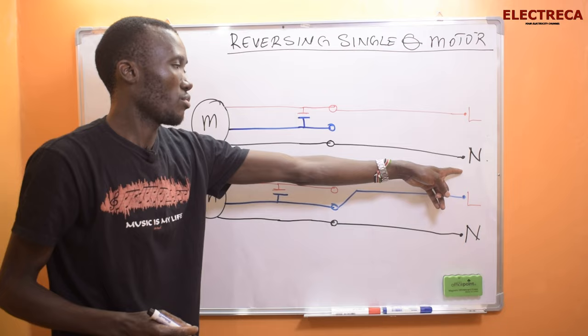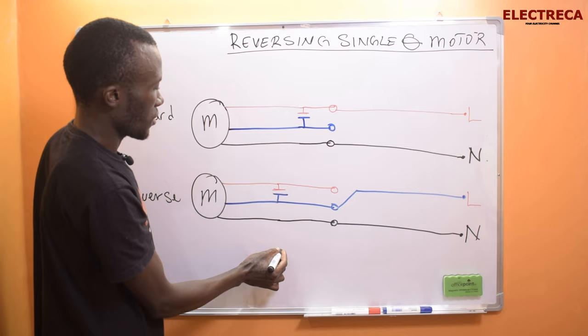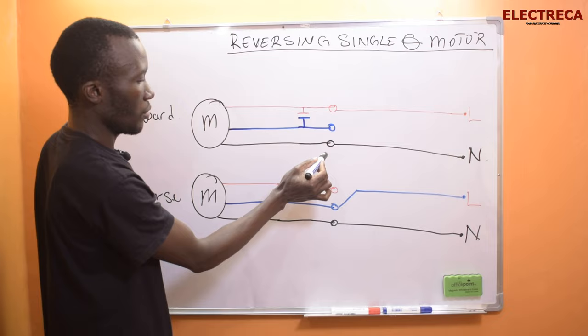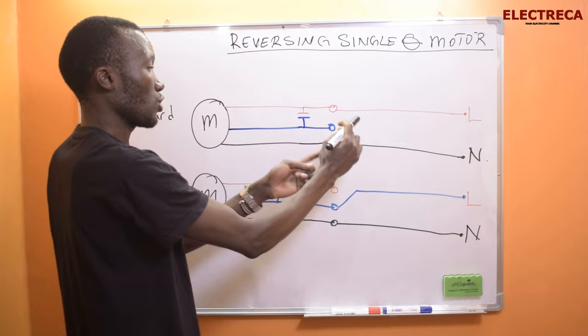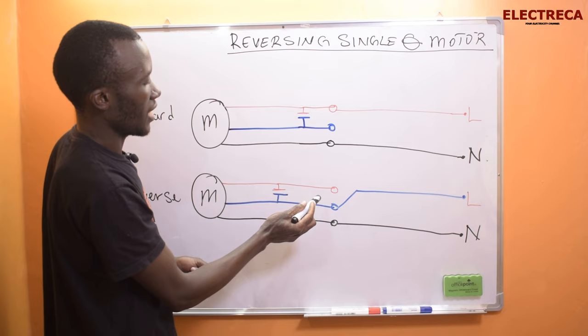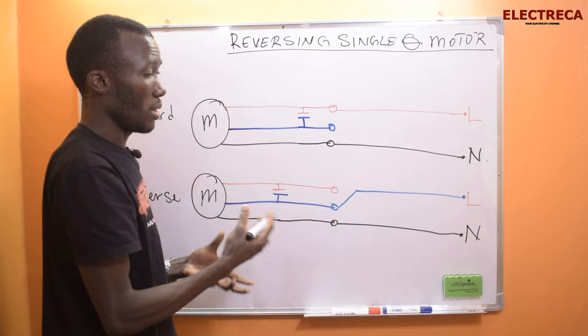The black wire connects to the neutral, so your motor will run in forward direction. Now when we go to reverse it, we still have three wires and the capacitor is already connected. The only thing you have to do is change the live connection from red to blue — the neutral black wire you just leave as it is. You're not swapping neutral and live; this is one phase. When changing, you must make sure you're switching between the two terminals of the capacitor, because the capacitor mimics another phase.